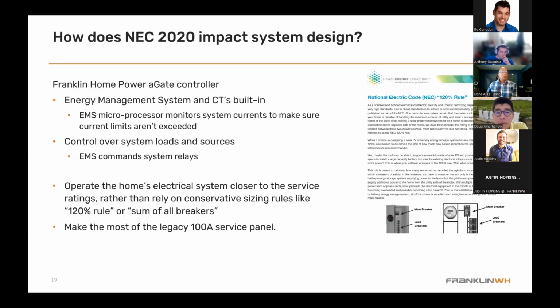I'm sure you've heard of the 120% rule and the headache it causes with sizing, plus the restrictions on load, PV, and batteries. That all goes away if you rely on the power control system and NEC 2020. That's a big one that keeps your customers happy and enables you to sell a larger system to them.